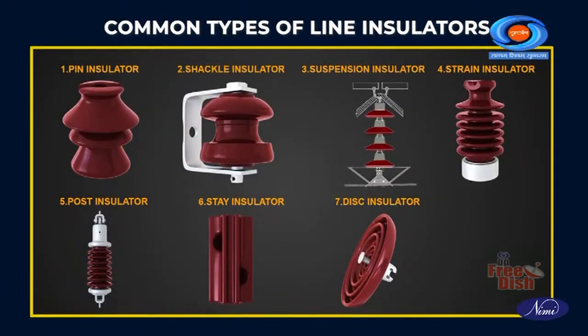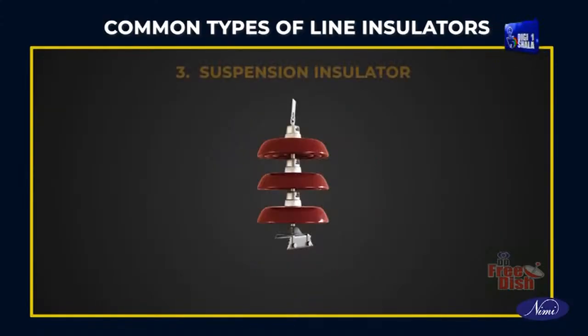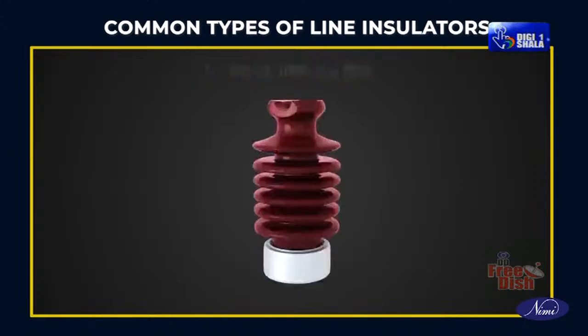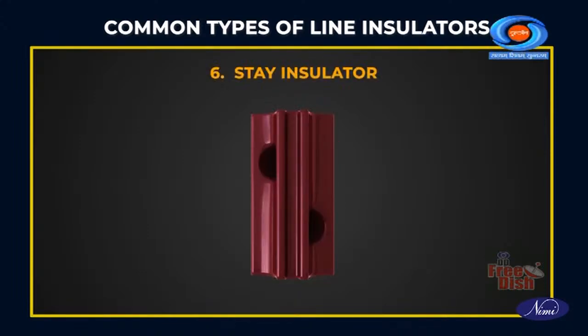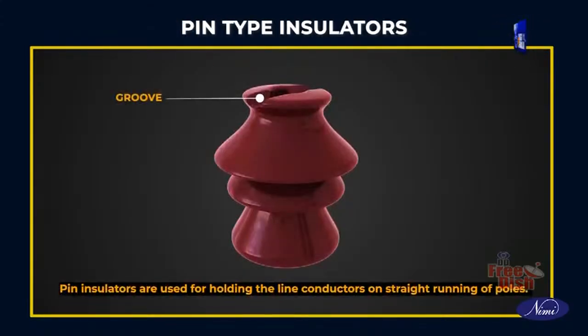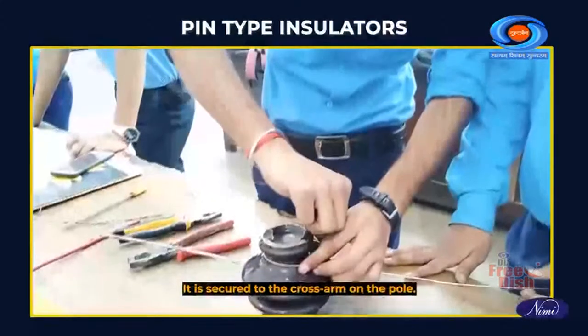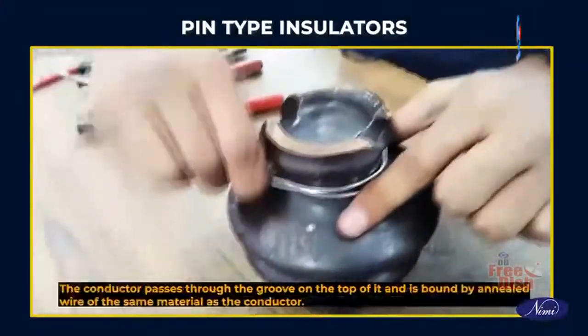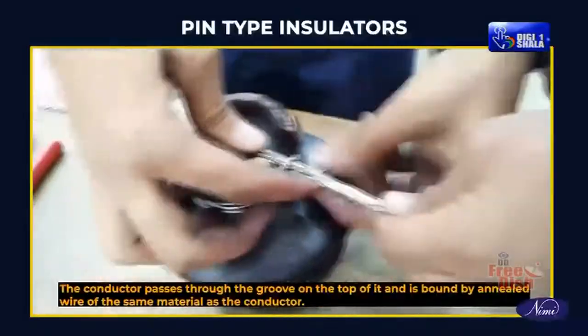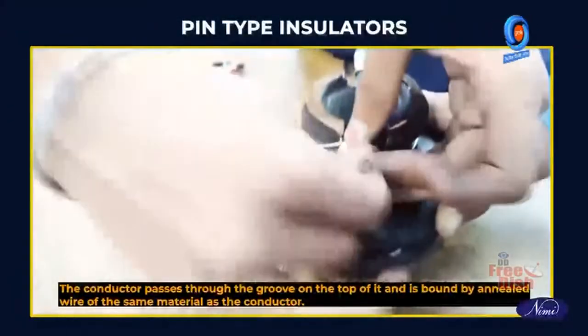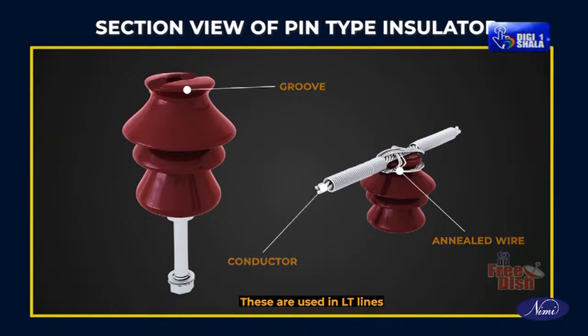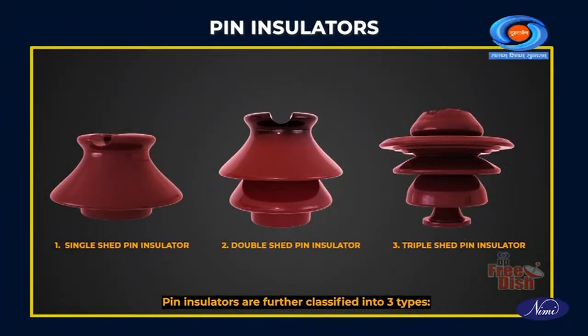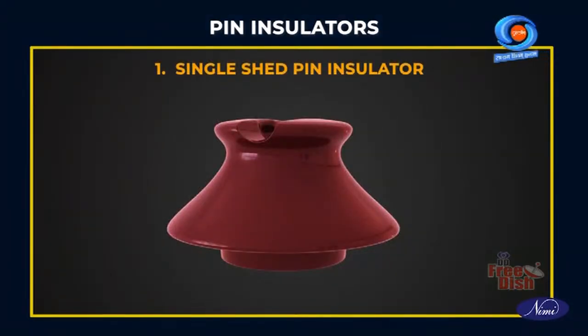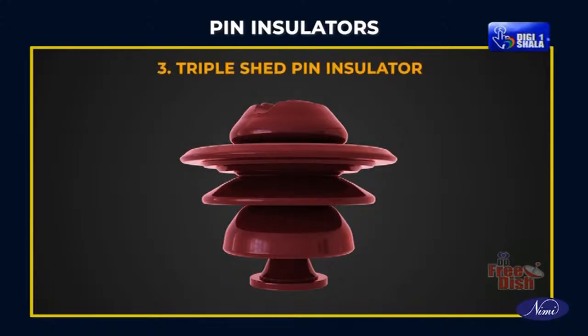Common types of line insulators: pin insulator, shackle insulator, suspension insulator, strain insulator, post insulator, stay insulator and disc insulator. Pin insulator. Pin insulators are used for holding the line conductors on straight running of poles. It is secured to the cross arm on the pole. The conductor passes through the groove on the top of it and is bound by annealed wire of the same material as the conductor. These are used in LT lines. Pin insulators are further classified into three types: single shed pin insulator, double shed pin insulator, triple shed pin insulator.